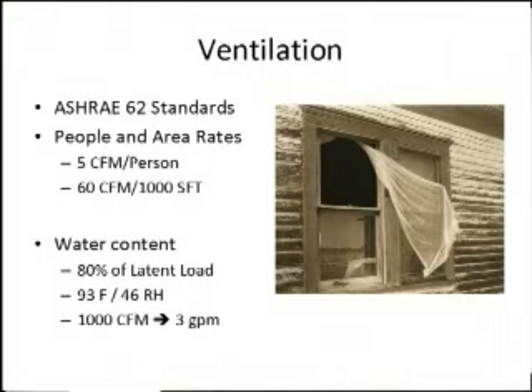People exhale CO2 when they breathe, and that builds up in a space. So we've got to bring in ventilation to remove that CO2, that carbon dioxide. And for the rest of the building, because we have carpet, we have paint, we have everything giving off the volatile organic compounds that we need to exhaust out of the space. So that's why ASHRAE split it up here and allows us to look at it 2 different ways.